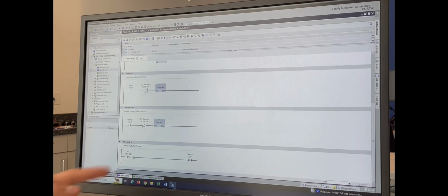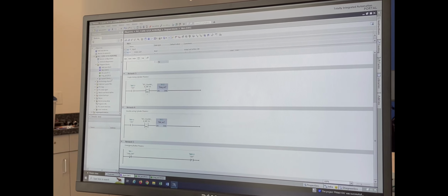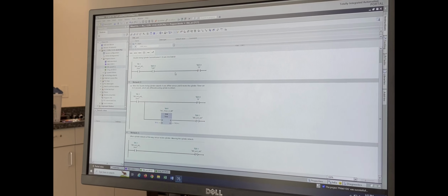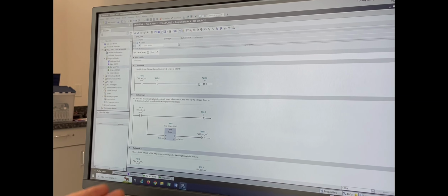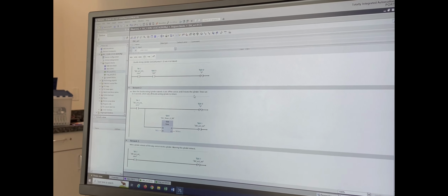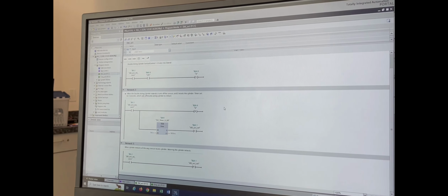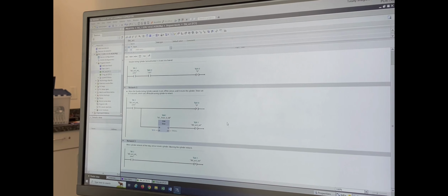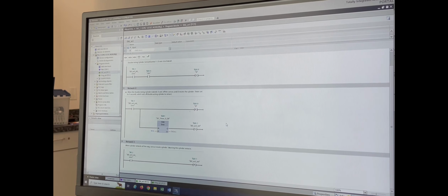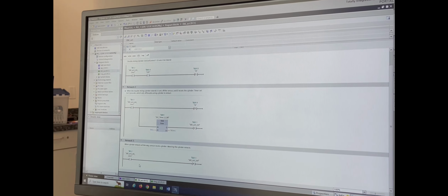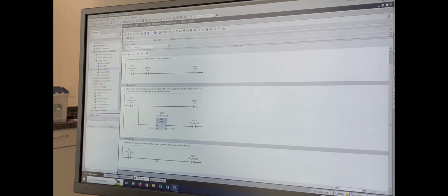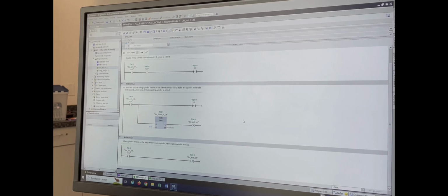And here we have an emergency stop button rung over here. Now I'm going to go into the double acting function. So, double acting cylinder here. Essentially what this does is it extends the cylinder based on this sensor, and it holds that for about 3 seconds before it resets and then retracts. Here is the double acting retract sensor. So it resets it here and then retracts.